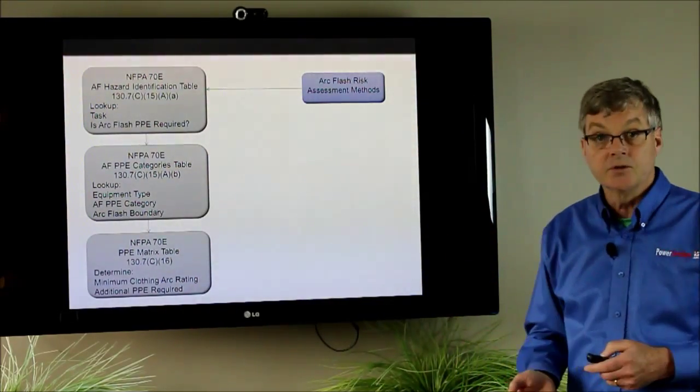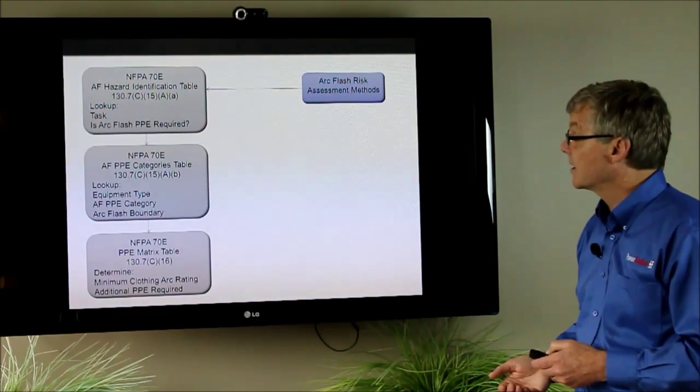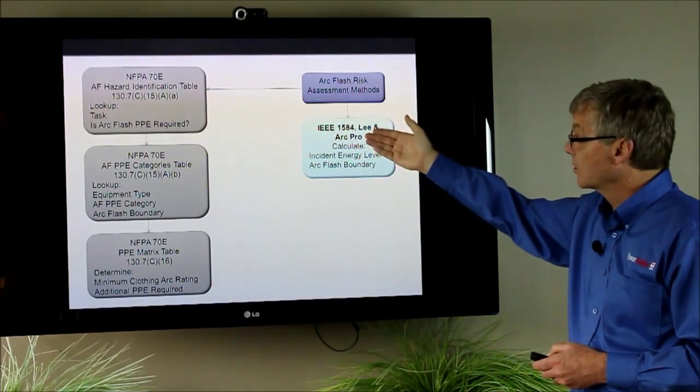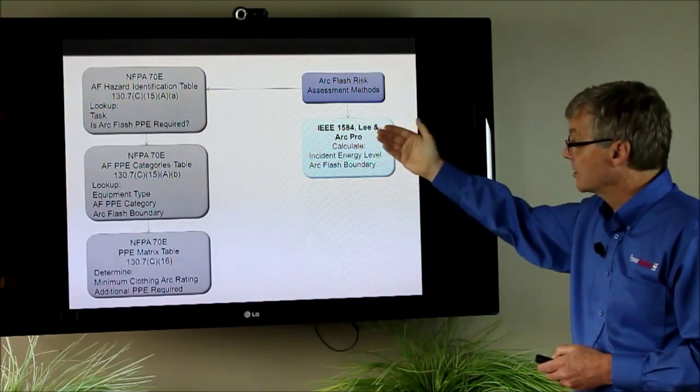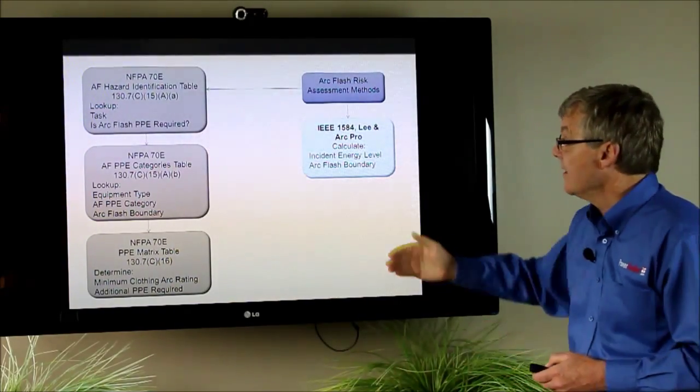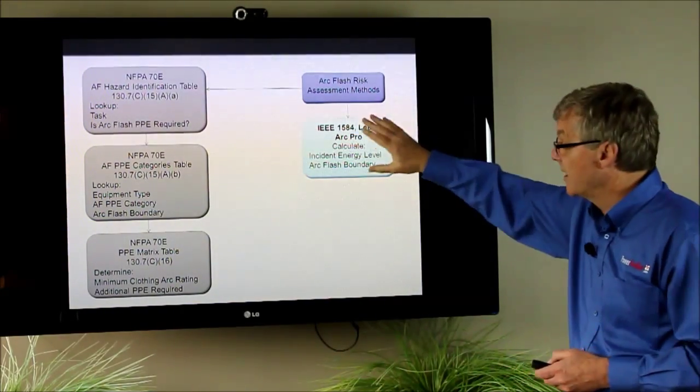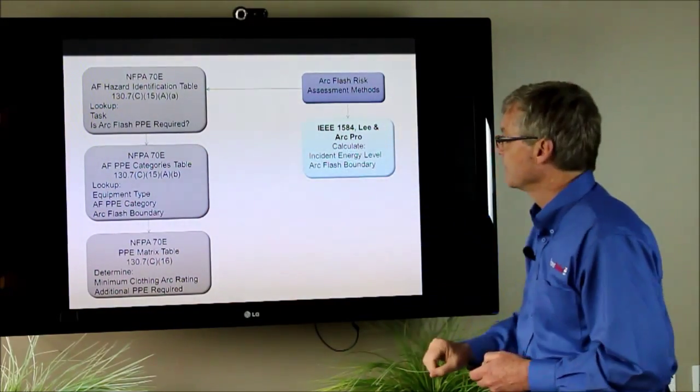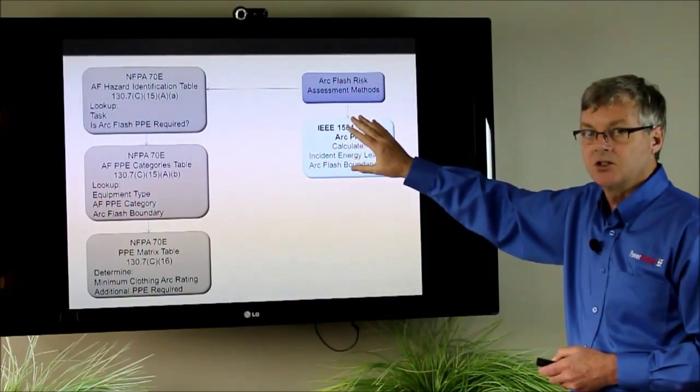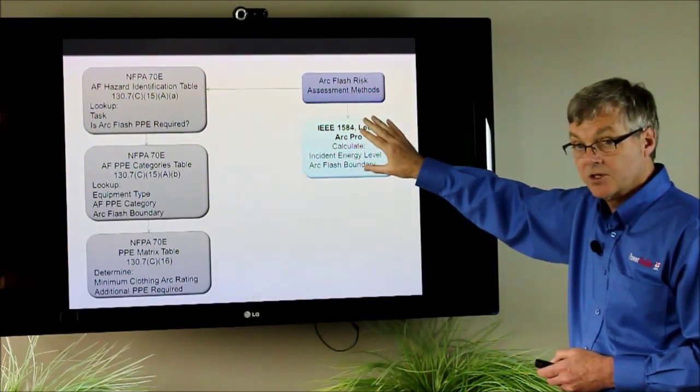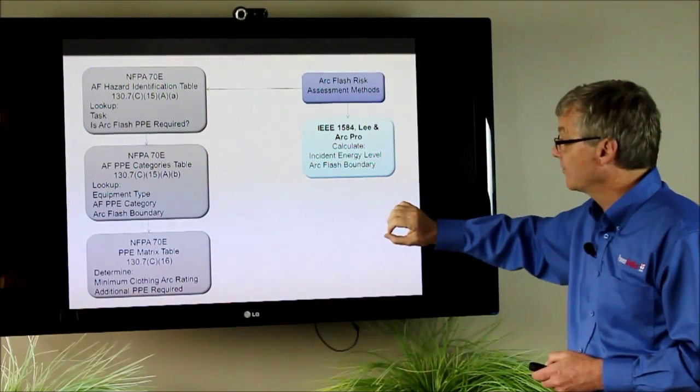The other way to do these arc flash studies and incident energy analysis is using the IEEE 1584 equations. The Lee equations or using arc pro to calculate your energy and the arc flash boundary. This method has nothing to do with risk, meaning risk is not a factor in it like this method is. Here we're calculating just the arc flash energy in calories per centimeter squared and what the arc flash boundary is going to be.